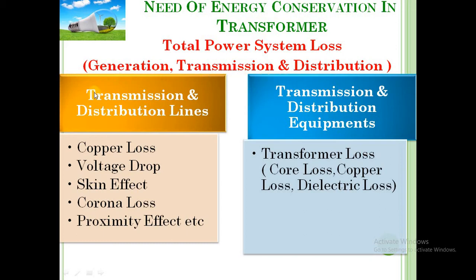So first we'll see line losses. Here I have listed a few losses which occur in transmission and distribution lines. First is copper loss, second is voltage drop, that is I into R drop, then skin effect, corona loss and proximity effect. So these are the losses which occur in transmission and distribution lines, and these losses will remain the same as the line is.